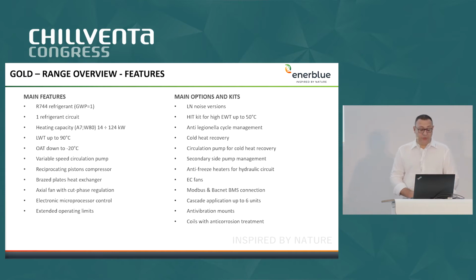The main options for these units are the low noise version and the HIT kit we spoke about before, in order to increase the allowable entering water temperature. There is the possibility to manage the anti-Legionella cycle by the unit. There is the cold heat recovery, as we spoke before. There is the circulation pump for the cold heat recovery available as an option. There is the possibility to manage the secondary pump on the circuit. There are also the antifreeze heaters for the hydraulic circuit, the EC fans for the unit, and the possibility to have communication with an external BMS or general controller with Modbus or BACnet.